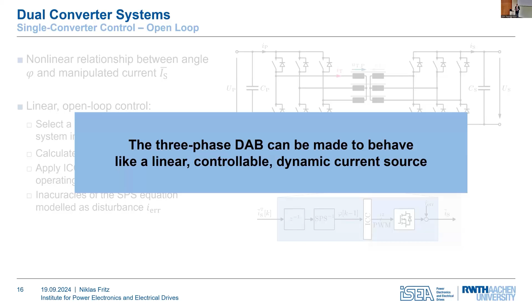The first thing you do is take your reference current and directly forward it to the converter, because the open loop control is already good. Then you can just take a measurement and use an integral regulator to compensate for the remaining error.